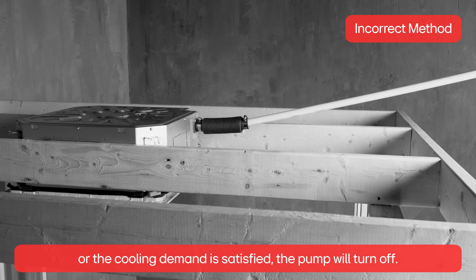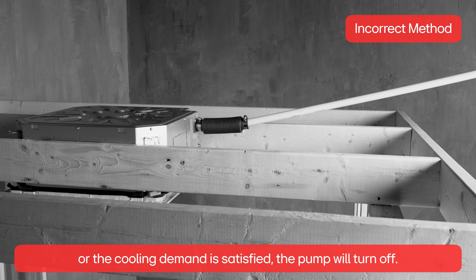When the unit turns off, or the cooling demand is satisfied, the pump will turn off. Excess water in the pipe will drain back into the unit and overflow the drain pan.